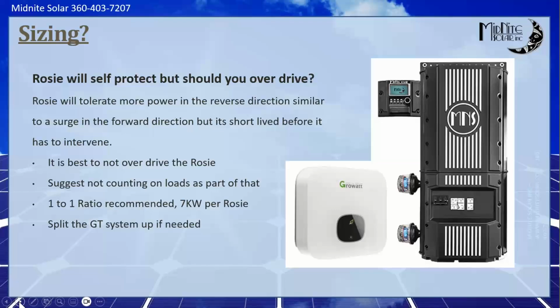But what that does allow you to do is run a true one-to-one ratio on the Rosie. So if you have a 7 kilowatt grid tie inverter and you get an edge of cloud and it bumps up to 8,500 watts or 9,000 watts, the Rosie doesn't care. The Rosie reacts the same way in reverse as it does in forward. It will watch temperature rise internally and it will regulate based on that. So eventually the temperature will rise because you're overdriving it, and it will frequency shift and knock the AC coupled offline. So with that being said, our recommendation is a one-to-one ratio.